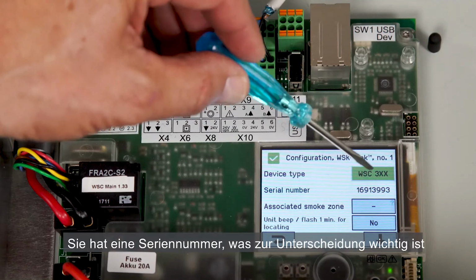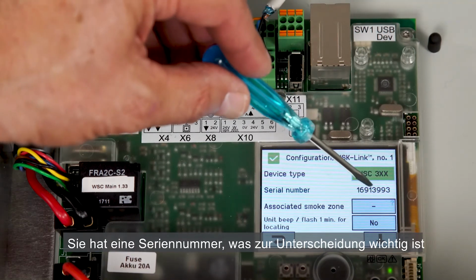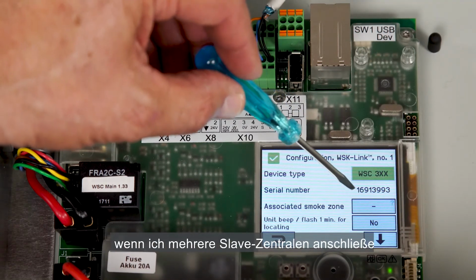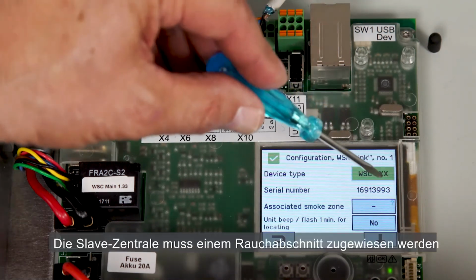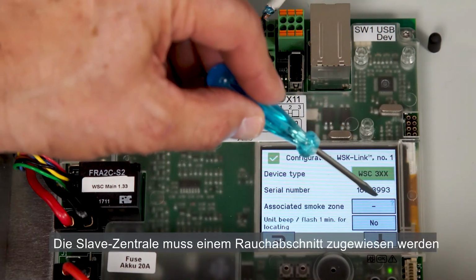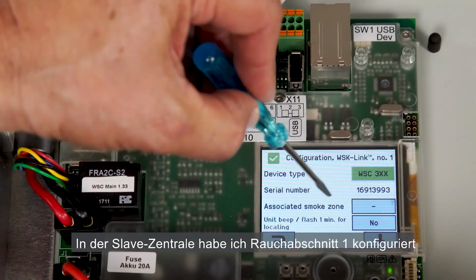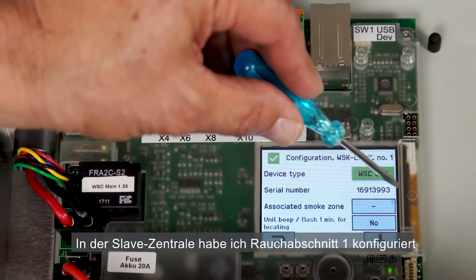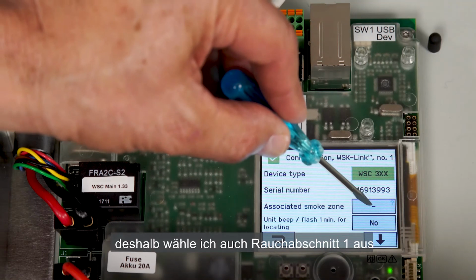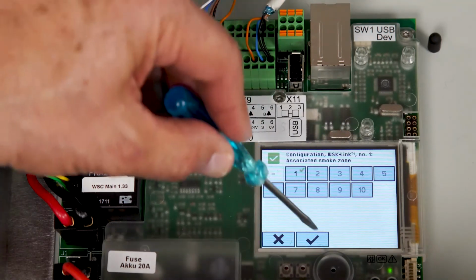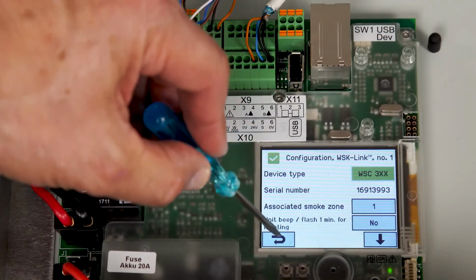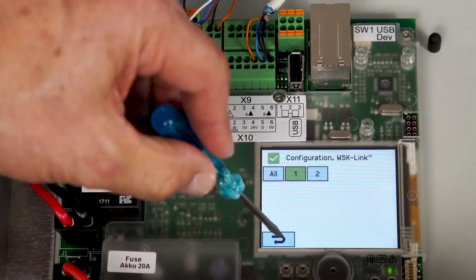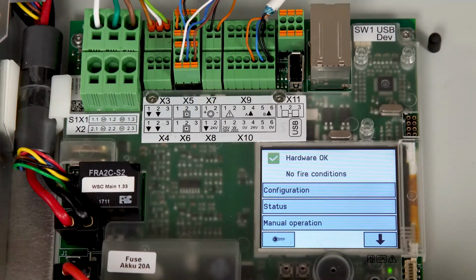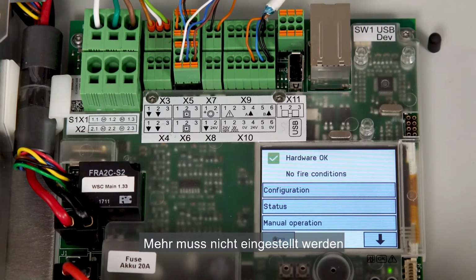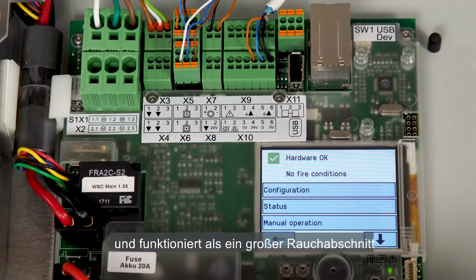It has a serial number in case I want to connect several slave panels to be able to tell them apart. I need to associate the slave panel with a smoke zone. On the slave, I have implemented smoke zone 1, so I select smoke zone 1. This is all that needs to be done. The system is configured and will work as a large smoke area.